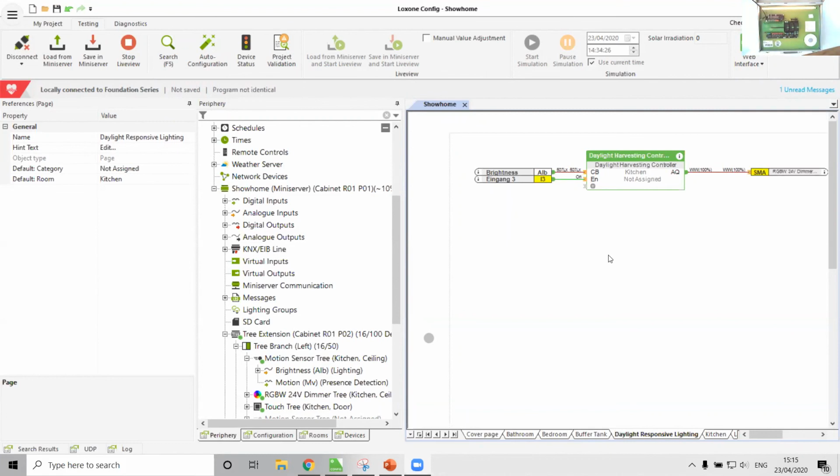And so now this is a good approximation of a proper office space with natural light streaming in. And what I've got here is, even with the natural light on today, we are just above 600 lux at 100% brightness. So it's going to keep that 100% brightness. Cool. And that is daylight responsive lighting.